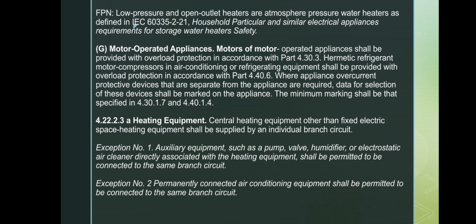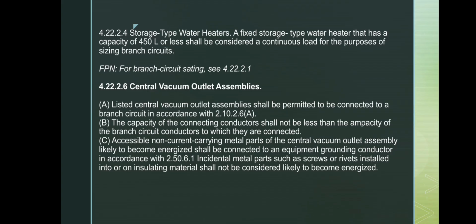First, auxiliary equipment such as pumps, valves, humidifiers, or electrostatic air cleaners may share the same branch circuit. Second, permanently connected air conditioning equipment may also be connected to the same branch circuit. Next is for storage type water heaters. Any fixed water heater with a capacity of 450 liters or less is treated as a continuous load. When sizing the branch circuit, the FPN reminds us to refer back to section 4.22.2.1 for the proper branch circuit rating.